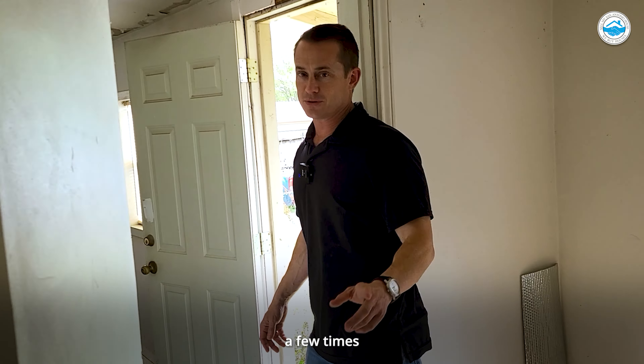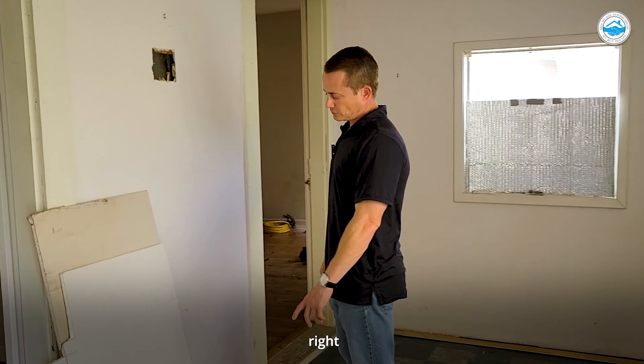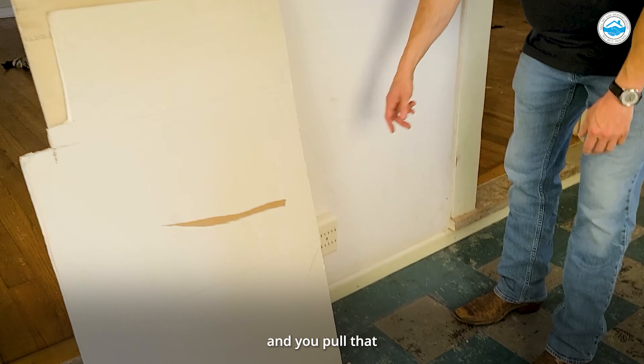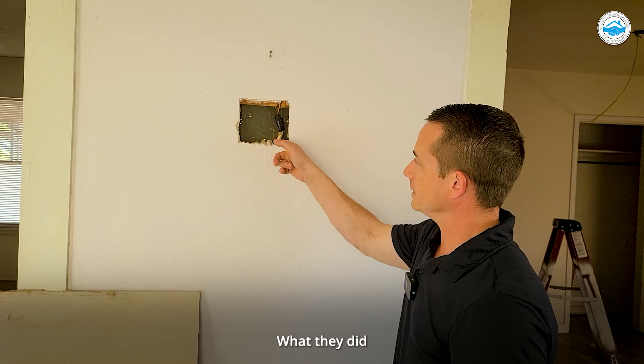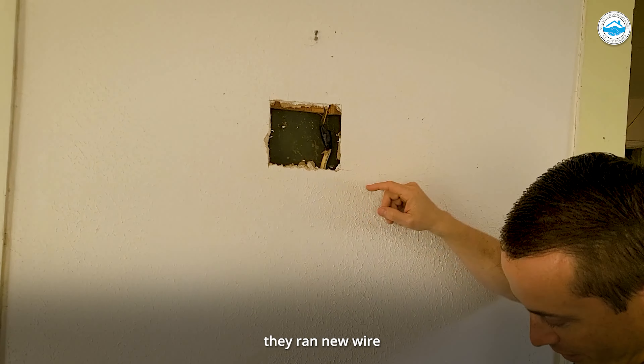This one we've seen a few times, but you don't see it all the time. You'll see a newer plug, and if you pull that plug off, you'll see newer wire in there and you come up the wall. What they did is they ran new wire from here to here, and they just tied into this old wire. This is obviously not correct.